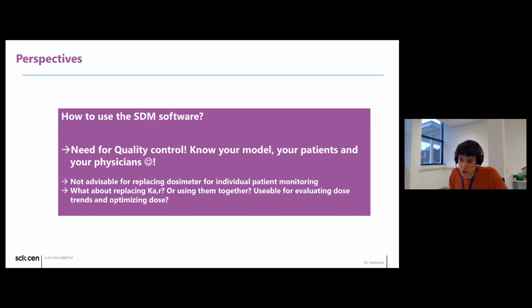And then really, I think it's too early to think about replacing dosimeters for individual patient monitoring. You have seen in the results that the accuracy can be very low in some cases, and anyway, who is performing measurements with dosimeters? That's true. And you can also think about what about replacing the air kerma and those metrics with maximum skin dose, or I would think even better, how to use them together. And so you should consider: are you able to evaluate those trends with the maximum skin dose? Are you able to optimize those?